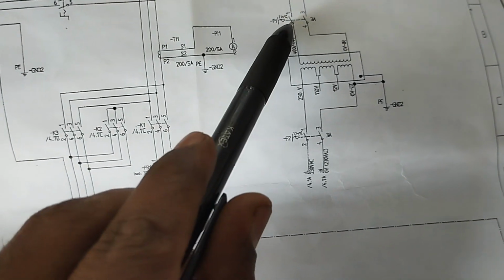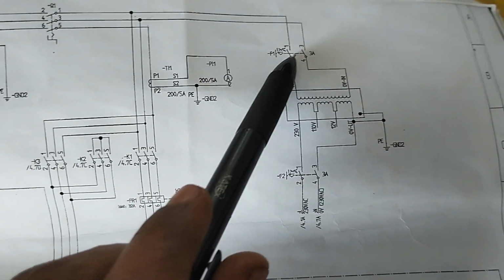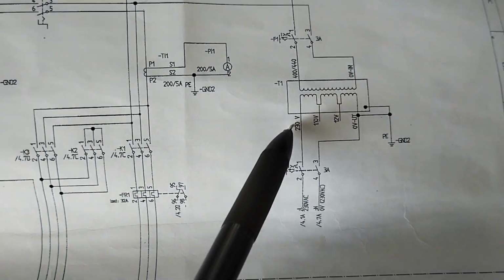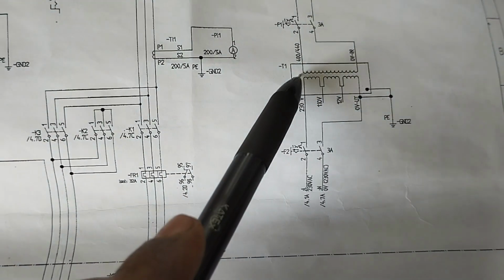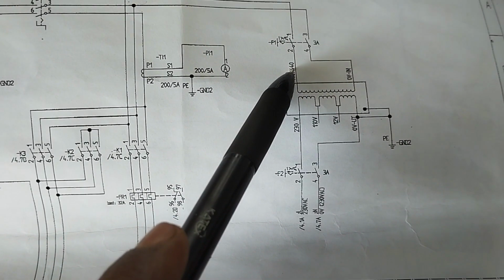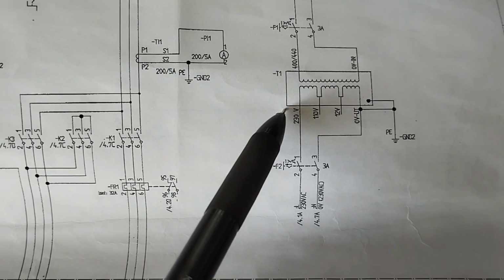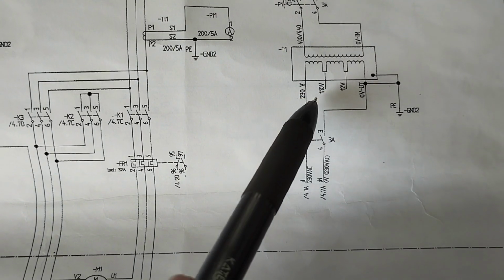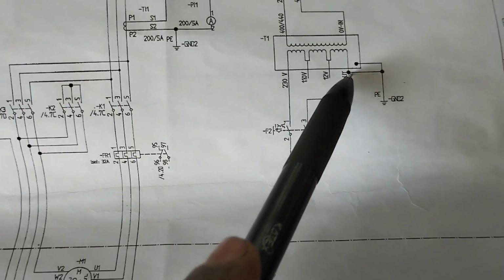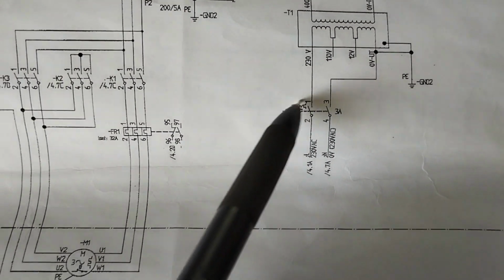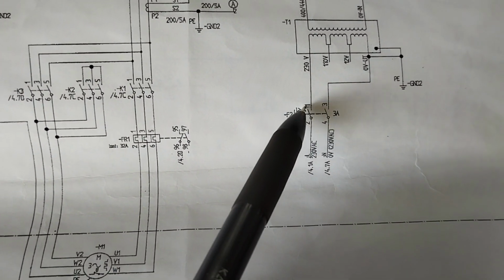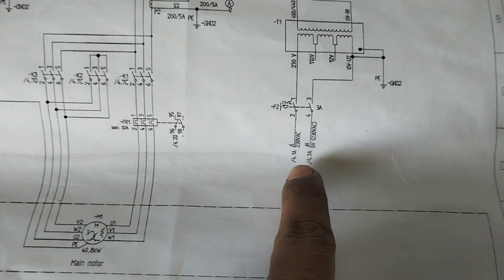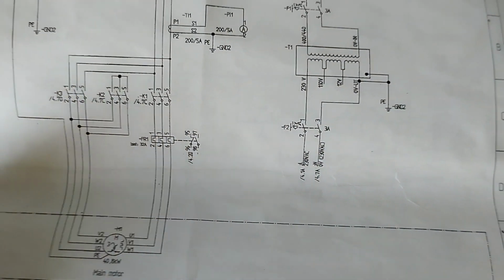So this is the L1 and L2, 440 power will come here. F1 is the circuit breaker for protection against short circuit, and this is the transformer. This is the primary of the transformer, you can see 440 volt, and these are the secondary various outputs. Okay, it's 220, 110, 12 volt and 0 volt. This is the common line. So this is the second circuit breaker for protection, MCB. After that power will supply to the control circuit. Okay, so we'll go to the next page.